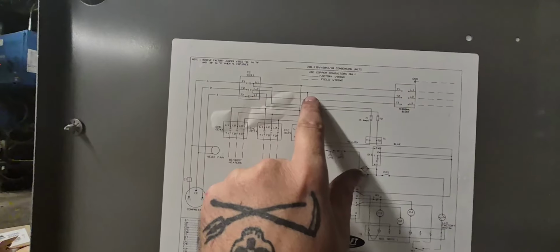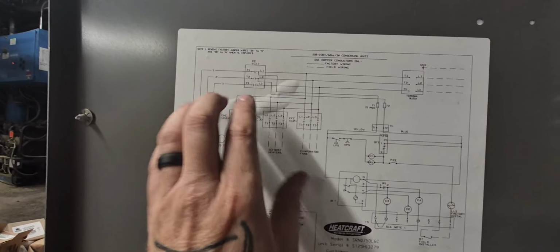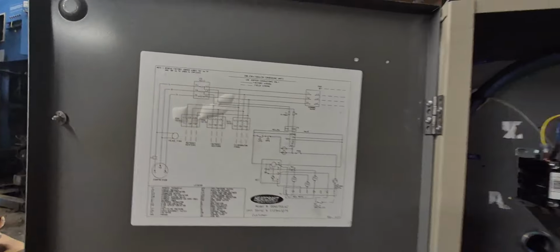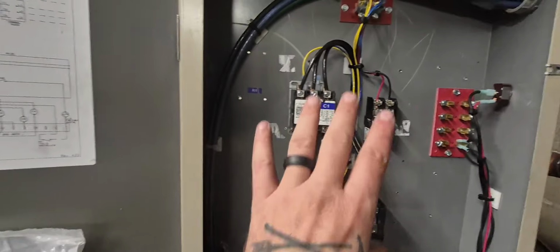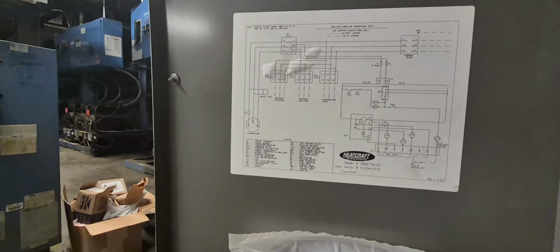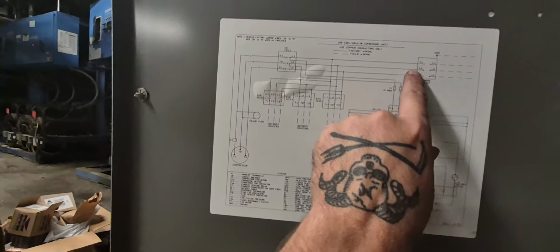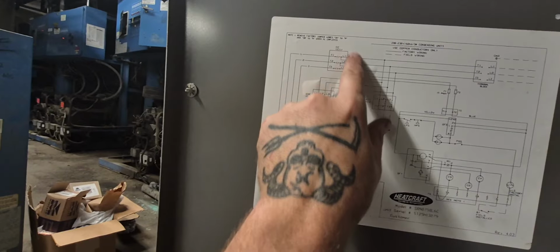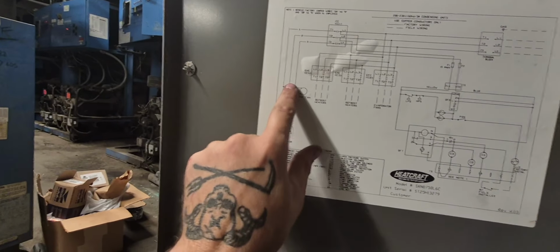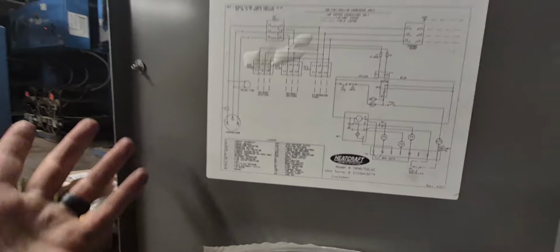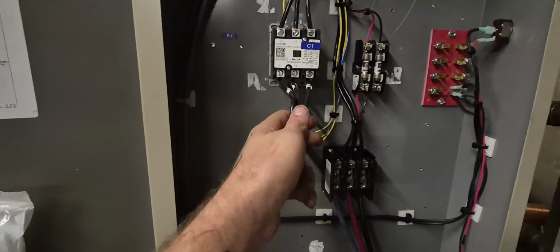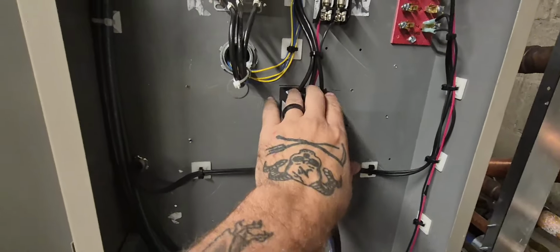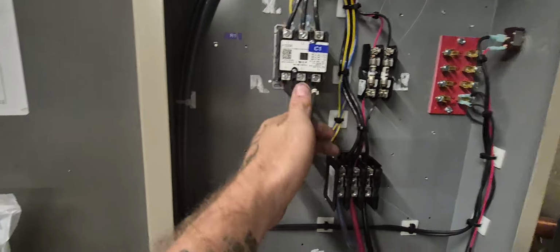Now here, obviously you see we've got stuff that branches off. All of this I eliminated, so I'm not too worried about showing you, because I can't show you a physical one right there. But that's our whole high voltage side, it comes through, hits our contactor, comes down, head fan, CT, compressor. Pretty simple, and you can follow that all the way, going in our terminal block, out of the terminal block, into the contactor, out of the contactor. And you can see if we follow this big conduit right here, it dumps us into our compressor head.